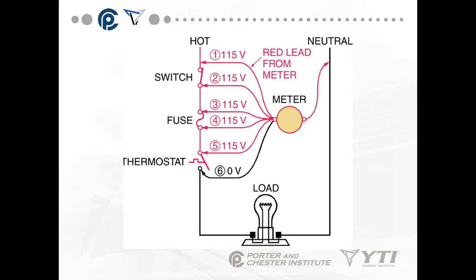With one lead on neutral, you work into the circuit one point at a time. When you go to the load side of the thermostat and get zero volts, you know you had voltage coming into the switch but not coming out. You have to find out why. With a thermostat, it could be bad, could have bad contacts, or it hasn't reached the proper set point temperature of the space it's trying to control.